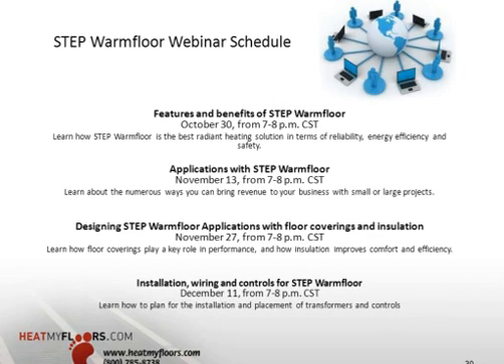Do you insulate underneath the heating product? Always. We're always going to stress that. There's never going to be a time when you talk to our sales representatives that they won't ask you, can you insulate underneath the system? We're going to try to do it underneath concrete, and if it's on a concrete slab, we'd like to see insulation done on that.